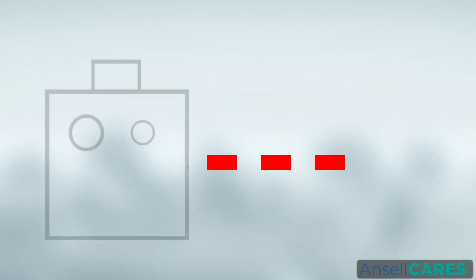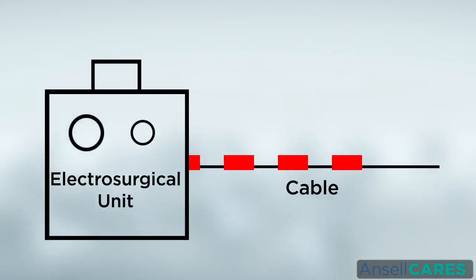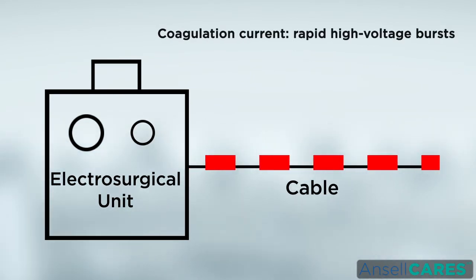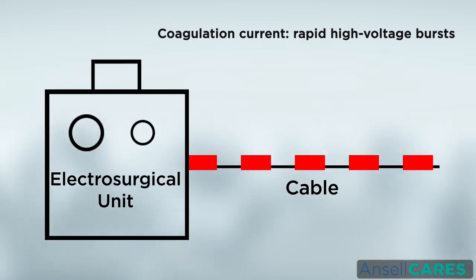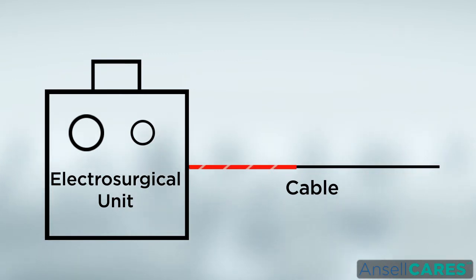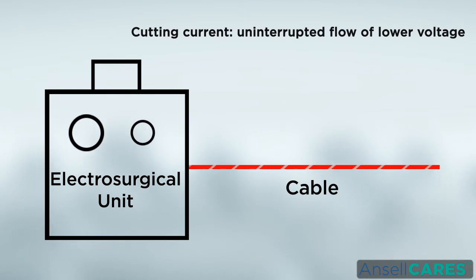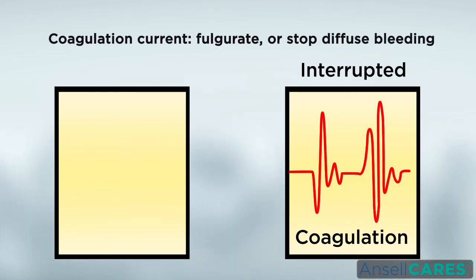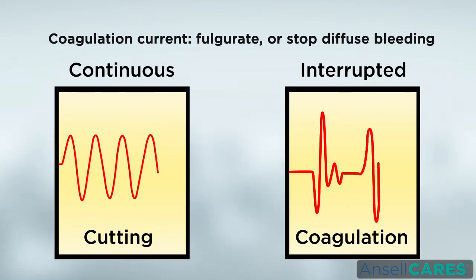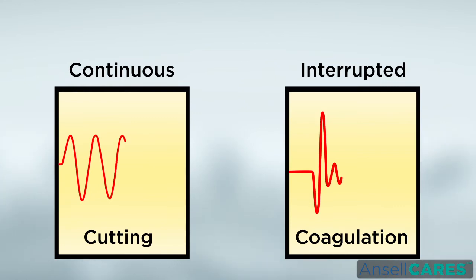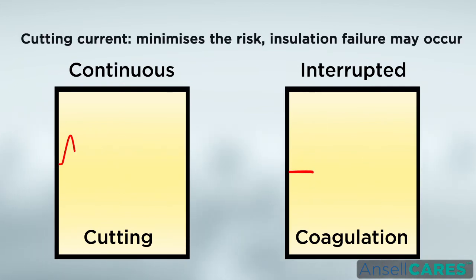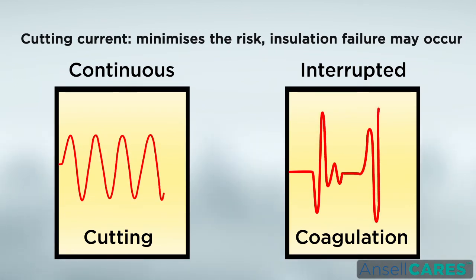Solution: usage of low voltage current is preferred. Electrosurgery equipment allows the use of coagulation or cutting waveforms of current. Coagulation current is released in rapid high voltage bursts to desiccate tissue and cause hemostasis, while cutting current comes out in a lower voltage uninterrupted flow to dissect tissue. In most cases, cutting current should be used for both cutting and coagulation. Coagulation mode is really only necessary when the need to fulgurate or stop diffuse bleeding on highly vascularized tissue is needed. Using the lowest voltage reduces wear on the insulation and minimizes the chance that current escapes through hairline cracks.